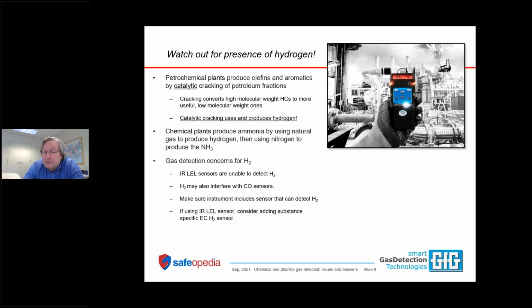It does not absorb. Molecules do not absorb infrared light. So they are IR invisible, which means you need to use a different method to detect the hydrogen. Hydrogen is also an interferent of carbon monoxide sensors.